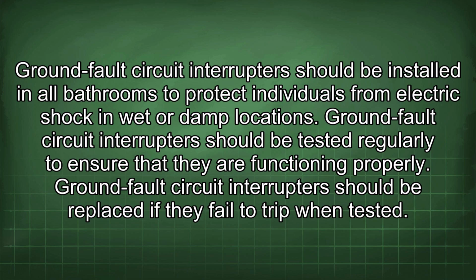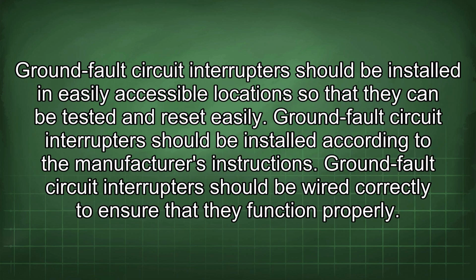Ground fault circuit interrupters should be tested regularly to ensure that they are functioning properly. Ground fault circuit interrupters should be replaced if they fail to trip when tested. Ground fault circuit interrupters should be installed in easily accessible locations so that they can be tested and reset easily. Ground fault circuit interrupters should be installed according to the manufacturer's instructions. Ground fault circuit interrupters should be wired correctly to ensure that they function properly.